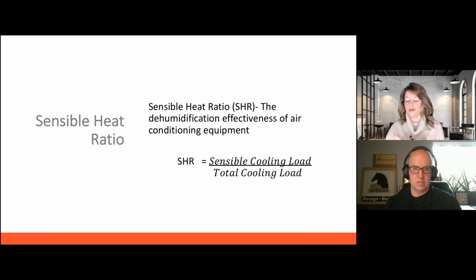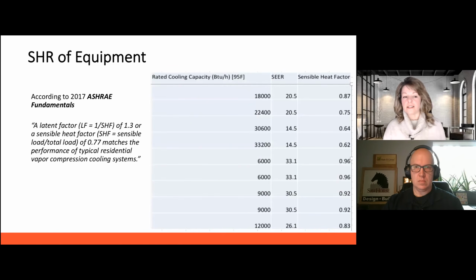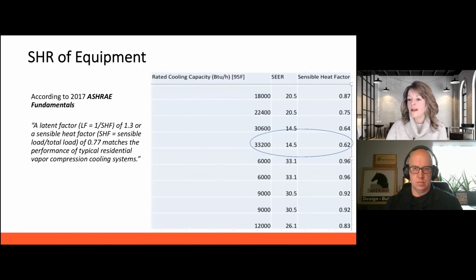So, sensible heat ratio. We are really trying to make sure the industry is becoming more and more educated on the sensible heat ratio, because this is the dehumidification effectiveness of the air conditioning equipment. And that number isn't real common on the data sheets, so sometimes you have to ask the manufacturer for those numbers. This is some data from a ducted and ductless mini split manufacturer. And just to show here, if we look at this, their 14.5 SEER system has a sensible heat factor of 0.62.